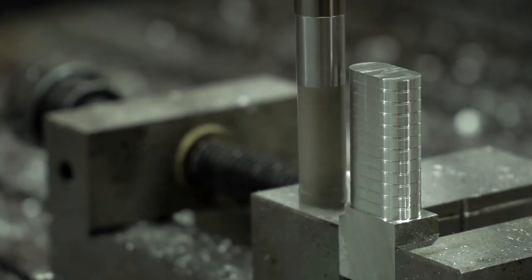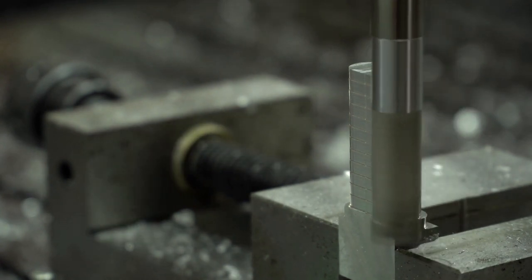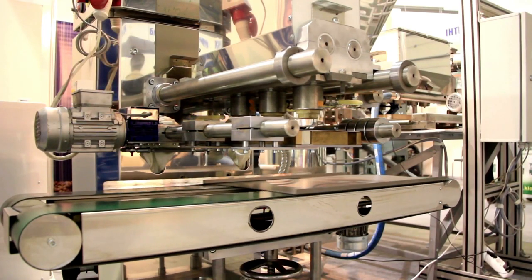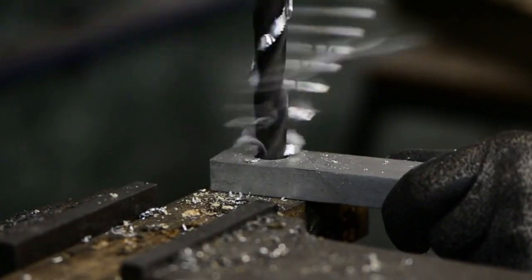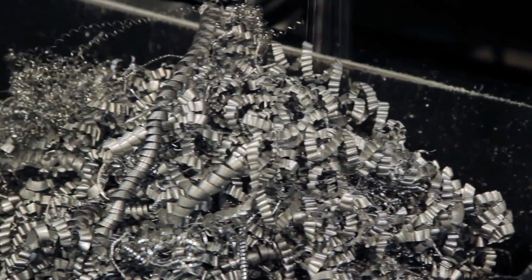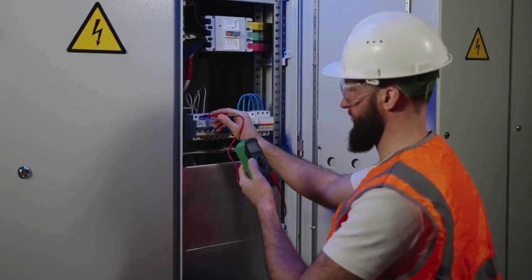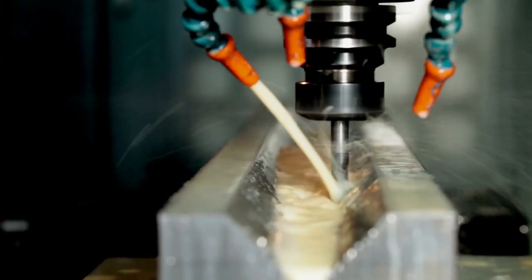Each machine on their shop floor is set up to do a number of machining operations on the aluminum workpiece. Being a multinational company, they have a huge production load, which means a lot of aluminum fines or burr to be handled by the coolant filtration system. In fact, the maintenance engineers identified coolant-related activities as the number one root cause for lost machining hours. A pump gets clogged or becomes defective, or they have to dismantle the tanks underneath the machines, or remove the conveyors because sludge gets built up in it.